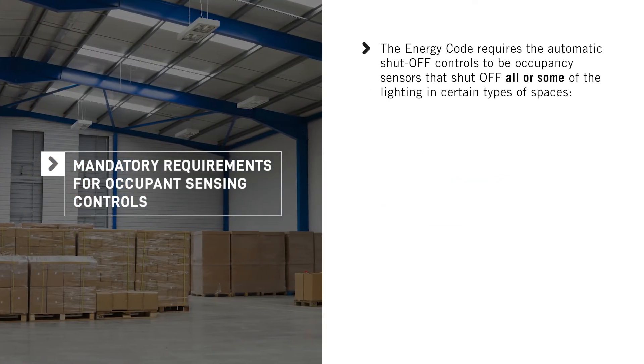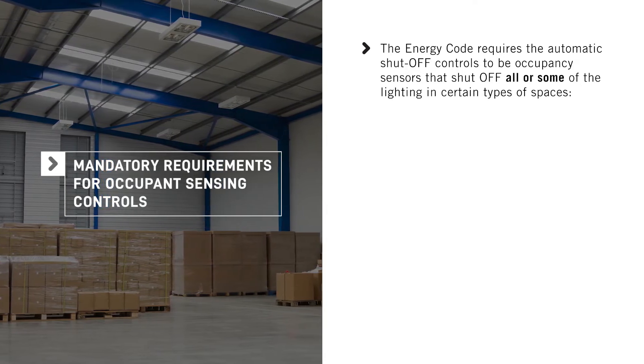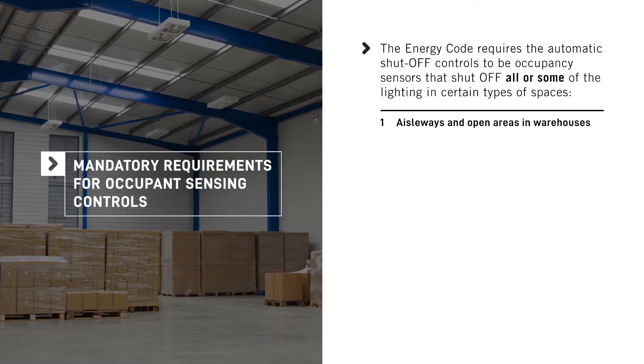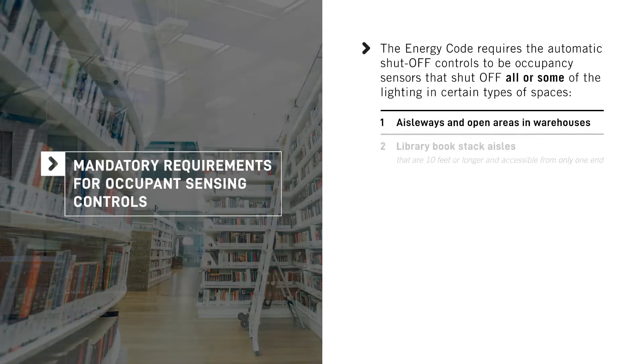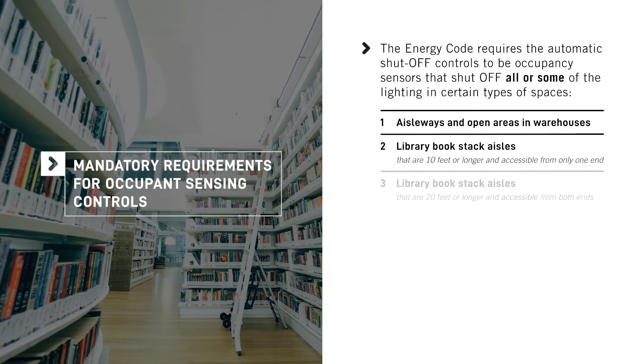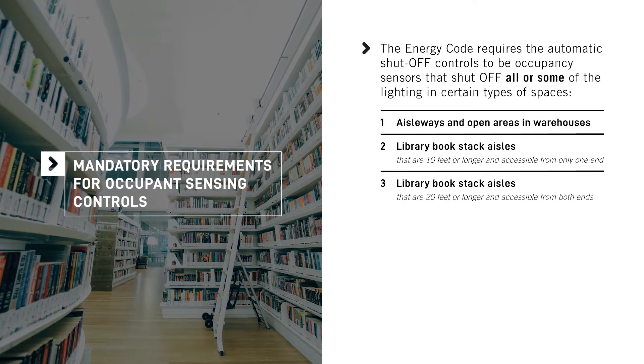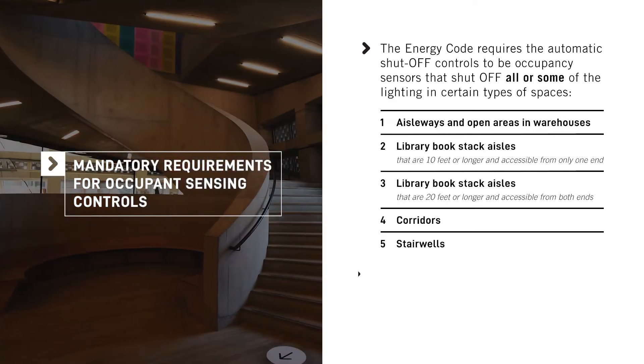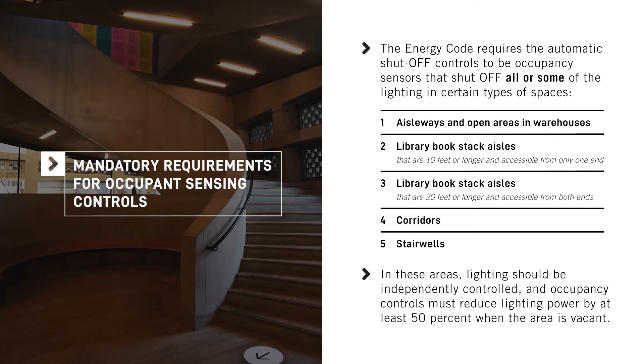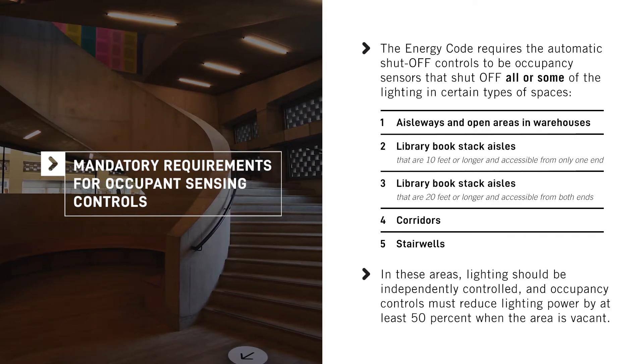The Energy Code also requires automatic shutoff controls to be occupancy sensors that shut off all or some of the lighting in certain types of spaces. These include aisleways and open areas in warehouses; library book stack aisles 10 feet or longer accessible from only one end; library book stack aisles 20 feet or longer accessible from both ends; corridors; and stairwells. In these areas, lighting should be independently controlled and occupancy controls must automatically reduce lighting power by at least 50 percent when the area is vacant.